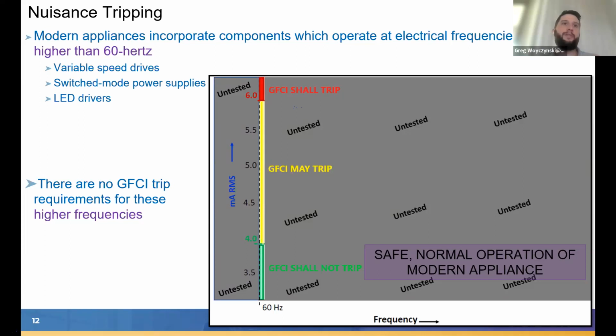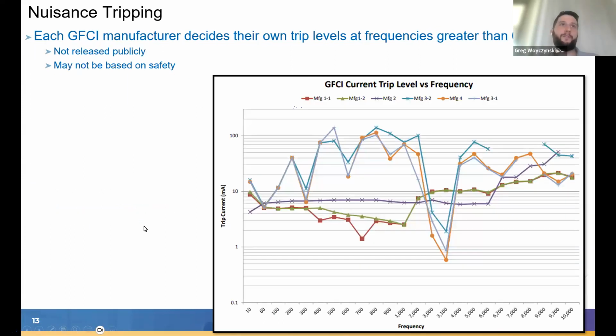The issue here is that there are no GFCI trip requirements for those higher frequencies. So we have this giant gray area here that is untested. It is up to each GFCI manufacturer to decide where they will and will not trip. And we have safe, normal operation of modern appliances in this gray area. So that's a big issue because GFCIs can trip all the way down here, even if it's safe. There's no UL requirement telling them they shall not trip. And we have proof of this.